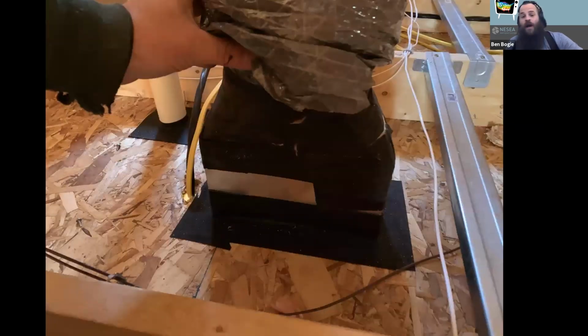Now I'm going to go right back on what I just said, and I'm transitioning to flex here, but for a reason. What you're looking at is this duct transitioning up through my ceiling, through our OSB air control layer — we use a rigid air control layer, and we can dive into that another time. You can see the 3¼ by 10 coming up here, transitioning to flex for about 3 feet, and it's all well sealed. This is critical — make sure all your ductwork is sealed.